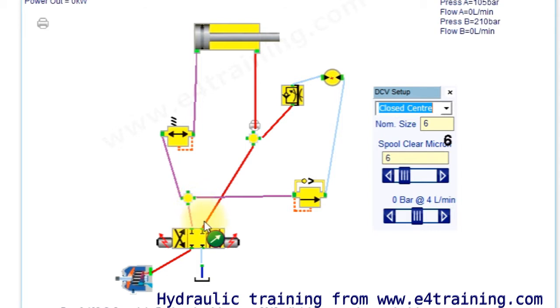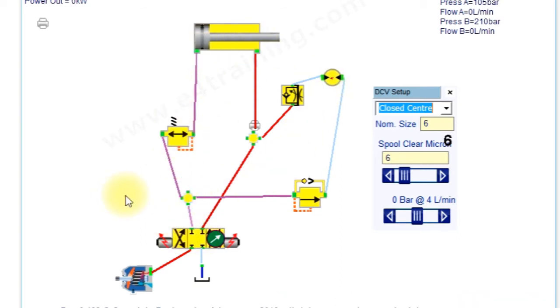But also, when we look at the circuit, the circuit is not ideal. We've got a closed center valve, so we've got pressure on these two lines. There will be pressure seeping from the input pressure line, so you probably get half the supply pressure on these lines. Different valves, different tolerances may vary a little bit. If we've got an unequal cylinder, which we have, that will drive the cylinder one way. If we've got loads on it, then it might drive it back. As soon as it starts to move, it releases pressure on one side and works the other side.